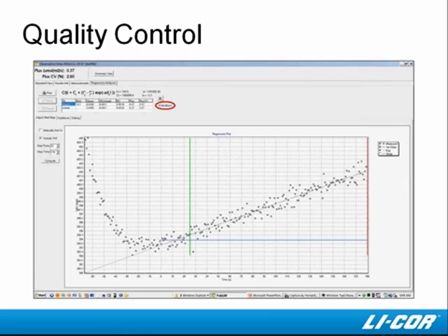While I'm on this slide, I might point out another observation. As you can see, the CO2 concentration before the chamber closed, during the negative times, was much higher than the CO2 concentration at closure. This occurs occasionally depending upon where the open chamber is set, whether it's over vegetation or some respiring material. You might get very high CO2 concentrations. As you set up your preliminary testing, you should look for this and be sure to add a pre-purge time so that you can get CO2 concentrations down to ambient before the chamber closes.